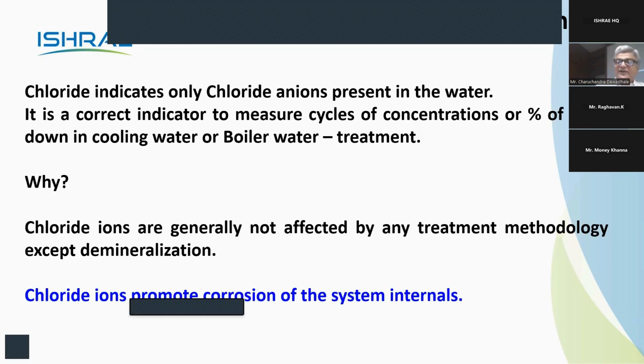Why chloride? Because chloride is generally not affected by any treatment methodology, except demineralization. Demineralization will remove chlorides completely and absolutely from the system, making it zero when the entire water is demineralized. Demineralized water has no cations, no anions, pure H2O is present - that is demineralization.